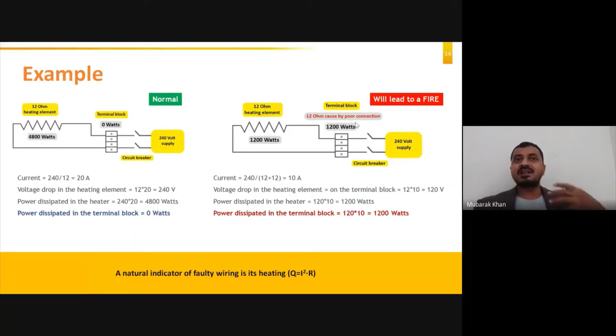So what will happen is, when there is a restriction to the flow of electrons, or a restriction to the flow of current, heat will be produced, and that heat can become sufficient to cause fire if there is any fuel present in the close vicinity. What is the normal fuel which is present inside the panel? It is the PVC insulation of the cable. At around 250 degrees Celsius, your PVC starts to melt and starts to burn. Okay. So the PVC may start to burn and it can cause a fire inside the panel. Now, if the temperature increases further, then there can be more disasters, which we will see in the further steps.